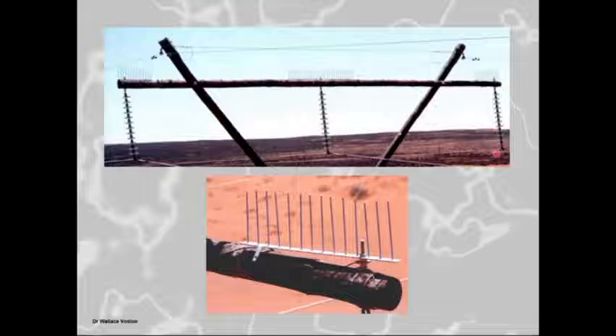So finally, we're back with Mr. Blue, and so we now present this. We write a paper about the insulator pollution flashover problem that wasn't, and bird guards were installed, and the line performance significantly increased to the level where we at this stage are not worried about the performance of the line anymore. I would not say this is the best bird guards to install, but these are bird guards. They worked quite well, and finally we managed to resolve the problem on that line.